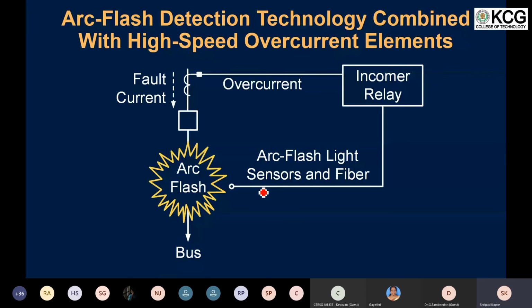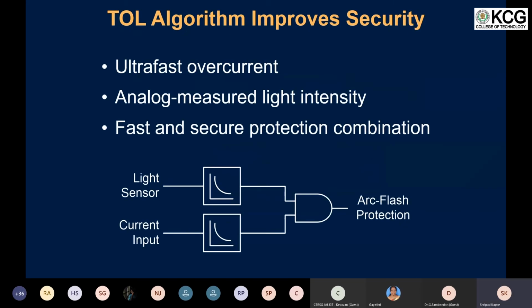In this case, what we basically do is mount sensors at some of the key locations in the switchboard, and then we take those sensors on a fiber optic cable to the incomer relay, and the incomer relay is anyway connected to the CT since it is providing the protection associated with the incomer. So both combined together, we are providing a solution to mitigate the arc flash energy. In order to achieve this, we use the ultra fast overcurrent principle. The ultra fast overcurrent principle in the relay, which is used for arc flash protection, acts much faster than the conventional overcurrent system. That is because of the filters that we are going to use in this particular algorithm.